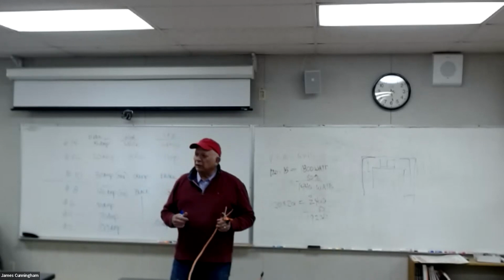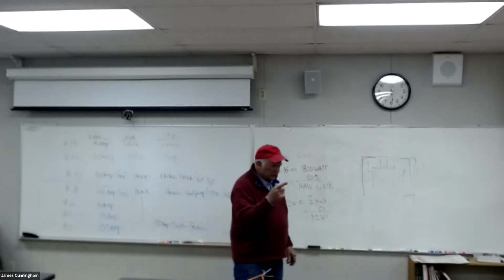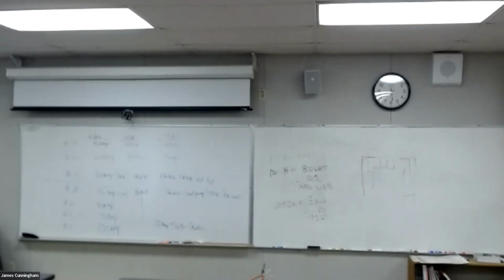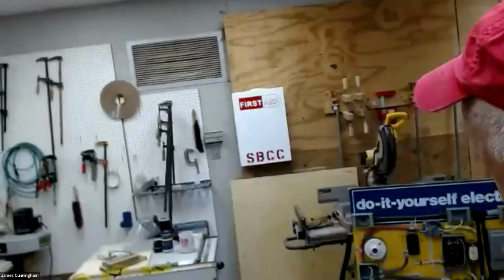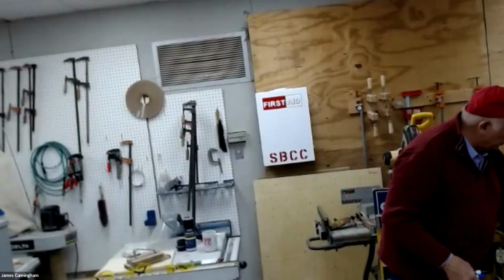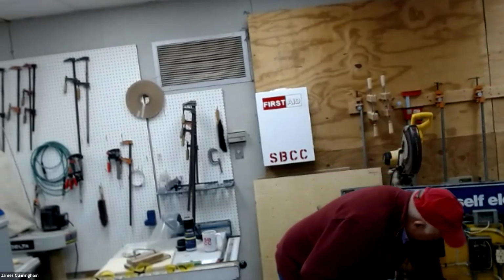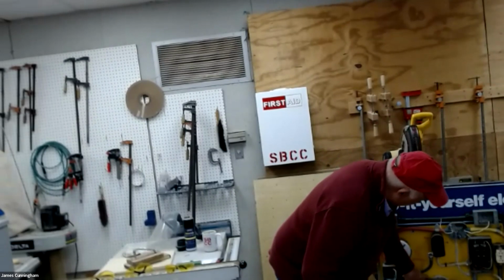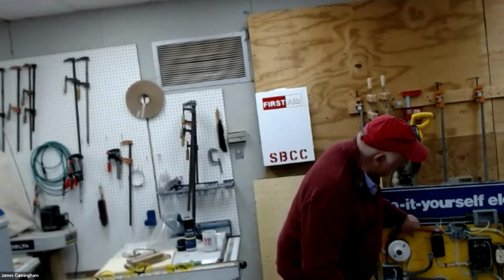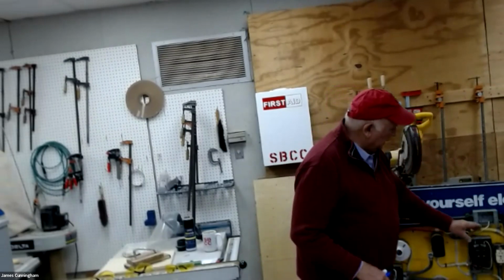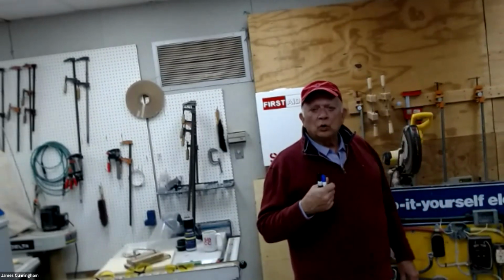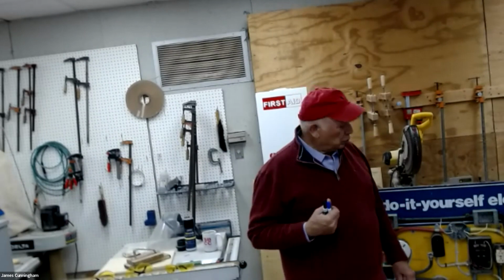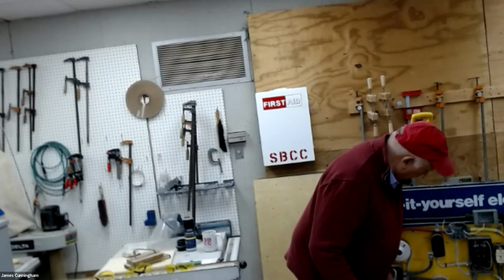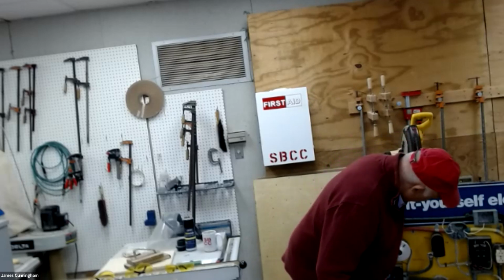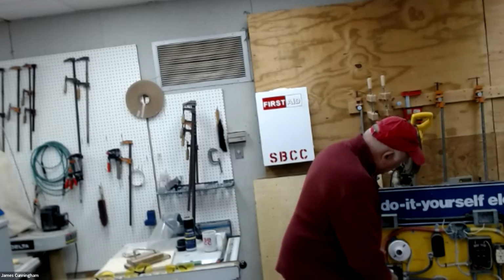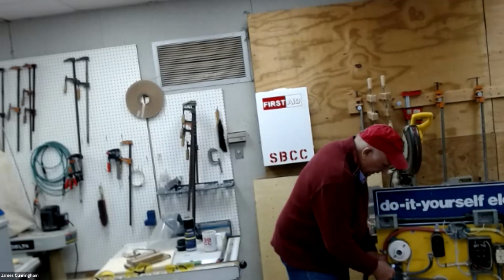Now, if I'm running my wires as individual wires through a conduit, and you can see on the panel over here that we have different kinds of conduit. We have weatherproof conduit, we have flex conduit here that's metal, usually either steel or aluminum. This is weather tight again, for outdoor applications. And then they have some plastic conduit here. But in these situations, you're not allowed to run Romex by code through a conduit. So you have to run individual wires. In that case, I would have a green wire for my ground. Oh, here's a green wire in my box. So the ground, you can always tell, is either going to be a green wire or a bare wire.